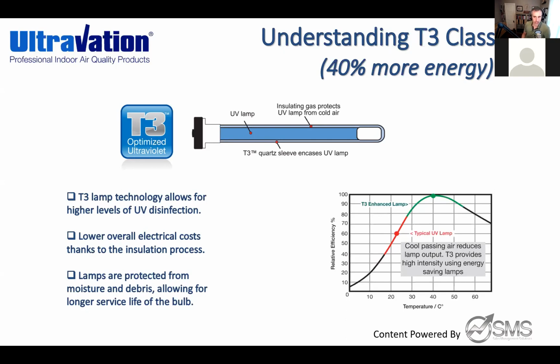The other great clarification here is that whether it's entry level or our T3, they're all 2-year warranted lamps. But one clarification in the industry is 2-year warranty does not mean 2-year life. Our T3 lamps actually have a 2-year life cycle. Standard UVC lamps are only a 1-year life cycle. They're guaranteed to still light up, but by the end of the first year burning 24/7, a standard UVC lamp has already burned through about 30 to 40% of its efficiency and effectiveness. So if you keep that bulb in there and don't change it out on an annual PM cycle, and it's not a T3 class lamp, you're losing a lot of its effectiveness.